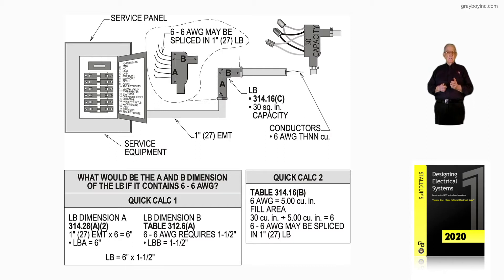Now, the LB dimension A, in accordance with 314.28A2, is one inch EMT times six equals six inches. So, the LB A would be six inches.